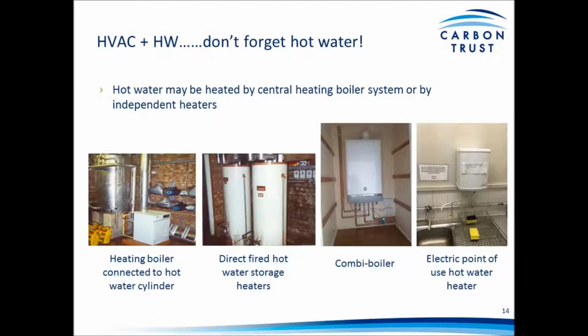Hot water can be heated by central heating via a cylinder or combi boiler, but it can also be by a separate dedicated system, such as direct-fired gas heaters or electric point-of-use units. And we typically find that dedicated systems often prove to be the most efficient arrangement, allowing central boiler plant to be shut down during summer months when there is no heating demand.